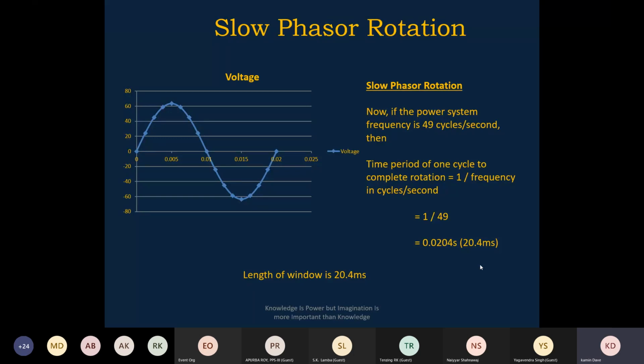So let us say slow phasor rotations. What is a slow phasor rotation? Let us say the power system frequency is 49 cycles per second, then the period, 1 divided by frequency, is equal to 0.0204, so 20.4 milliseconds. So the window of 20 milliseconds per cycle has now increased to 20.4. That is how the power system cycle window has increased.